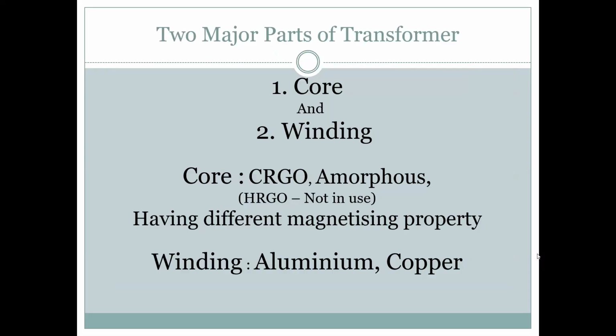Now basically it's a core and winding. Core is steel, winding is copper, but development is still going on. Core is CRGO, this is a special steel. Here the metallurgy comes into the picture. CRGO is cold rolled grain oriented. Whatever the metallurgy involved in the steel is a particular grain formation. So when this steel is produced, flux will go through it, it will consume less power, deliver less losses, and give maximum possible efficiency, and the self-consumption of the transformer will be minimum.